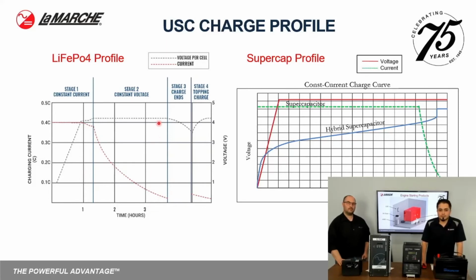Moving into your stage 3, once you do get down to that trickle charge, because it is a lithium iron phosphate battery, you do not require any type of trickle charging or any floating at this point. So at stage 3, you would actually end your charging, and then we would have a stage 4 charging, where if it senses a voltage dip, you would go ahead and turn it back on and top off the battery.